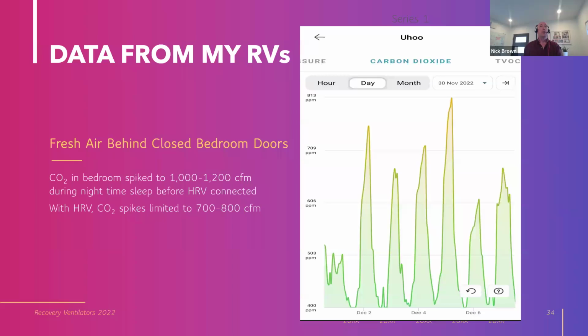Because keep in mind, your HVAC system isn't running all the time. And even if it is, it's recirculating air inside the house. So CO2 tends to accumulate behind a closed door in a room, especially when you've got 2 people sleeping in there. Once I put in an HRV port, I think it's 20 CFM or something, not a whole lot, the spikes were limited as shown here, more like 700, 800 parts per million. And the hope is we're getting more successful sleep as a result of improving the indoor air quality.